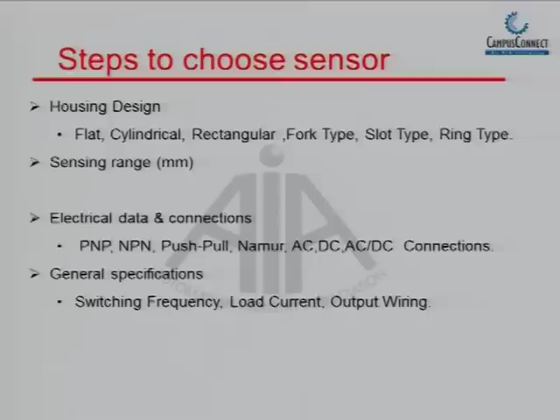Secondly, the most important factor is the sensing range of the sensor. If we have a target at a distance of approximately 10 mm, we cannot choose a sensor with a smaller sensing distance. Then the electrical data, that is how we are going to connect the device to take an input of this device. Either it has to be taken to a PLC. Now, if the PLC supports PNP type of input or NPN type of input, either it can be NAMUR, AC, DC. Based on that, we decide the electrical data and connections. And lastly, the frequency, that means the switching time of a sensor, how fast the device is moving in front of the sensor. Based on that, we decide the switching frequency of the sensor. So, these are some of the basic parameters.